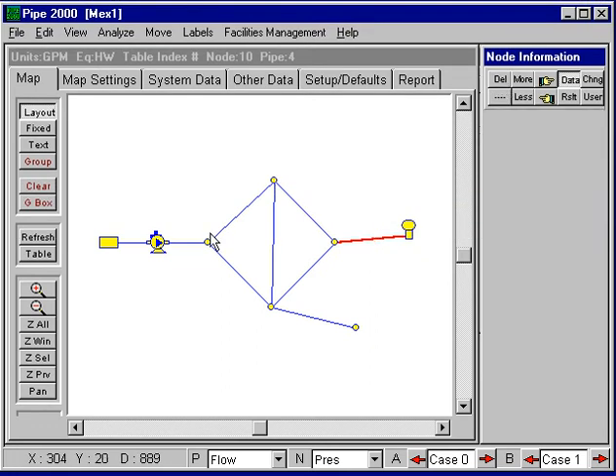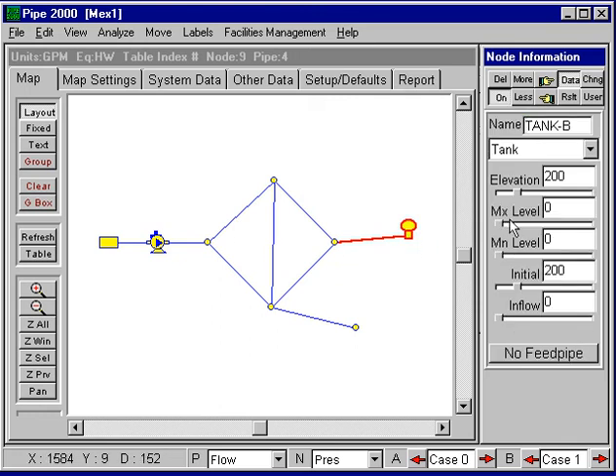The next thing I do is provide tank data for the tank, make sure we have the data. To run a regular simulation, all we need is the initial level. But to run an extended period simulation, we need the maximum and minimum levels, which I'm going to set at 220 and at 180.